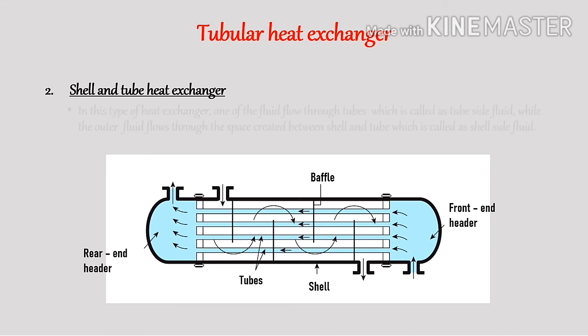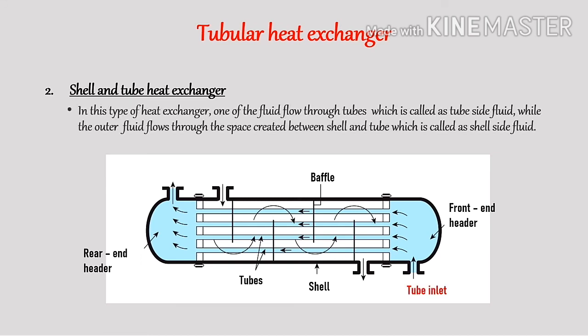The second type of tubular heat exchanger is the shell and tube heat exchanger. It consists of parallel tubes, a shell, baffles, and front and rear heads. The end of each tube is fixed in the tube sheet. The tubes provide the heat transfer area. One fluid flows through the tubes while the other fluid flows through the space between the tubes and the shell. Heat is transferred from the hot fluid to the cold fluid through the metal wall. The shell and tube heat exchanger is the most commonly used type in the chemical industry.